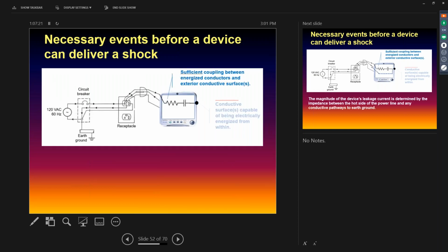The second thing we need is sufficient coupling, that RC coupling between the hot side of the line and the case. If you have coupling that's only going to give you 10 microamps of maximum leakage current, that's not sufficient. You'd have to have sufficiently high capacitance, low resistance to cause sufficient coupling to that conductive case.